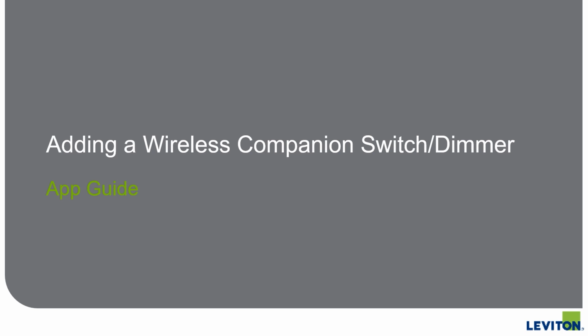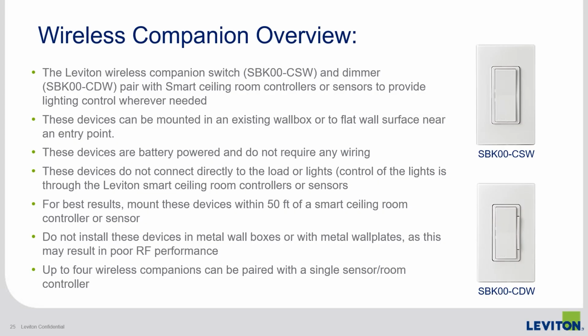In this next section, we'll show you how you can use the app to pair with one of the optional wireless companion devices. For applications requiring manual control, you can hardwire PLVSW keypads or use one of the SBK00 wireless companion devices. These are true wireless devices that are battery powered and do not require any wiring. They are mounted in an existing wall box or directly to a flat wall surface. For the best results, they should be mounted within 50 feet of a smart ceiling mount sensor or room controller. Up to 4 of these SPK00s can be paired with a single sensor or room controller.